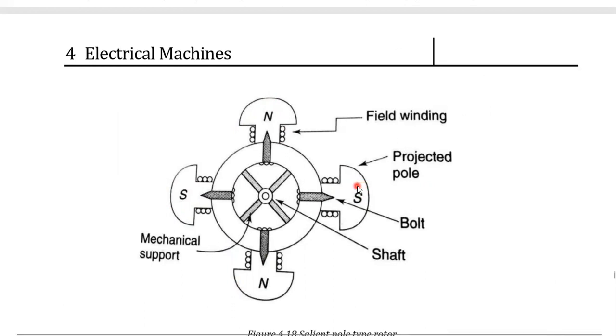When the speed is increased beyond the rated speed, or when the speed is decreased, the speed of the rotor changes. If the rotor is rotating below synchronous speed, the damping torque comes into the picture. It provides additional torque, called damping torque. When the motor is rotating above synchronous speed, an opposite torque is developed in the damper winding, and it reduces the speed to synchronous speed.